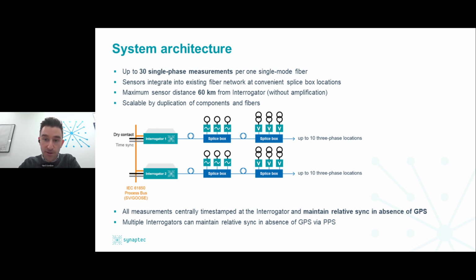Now, importantly, because all these measurements are centrally time-stamped by the interrogator, every single sensor deployed down that fiber will maintain relative time sync, even in the absence of GPS signal. So any protection functions deployed on that system will continue to operate even if GPS is interrupted or lost. And multiple interrogators can be coupled via PPS so that you don't lose relative time sync in your entire system, even in the event of loss of GPS.